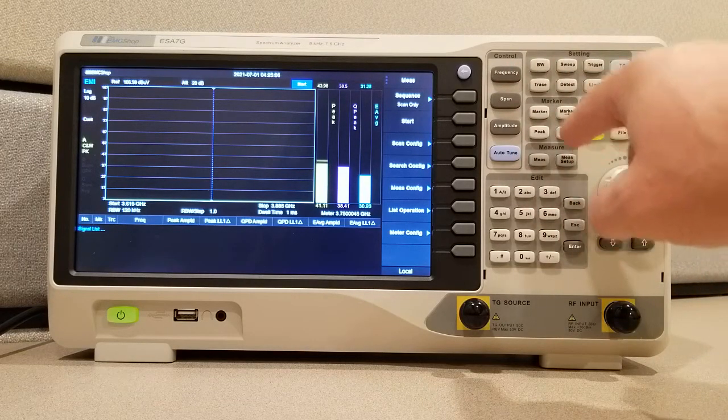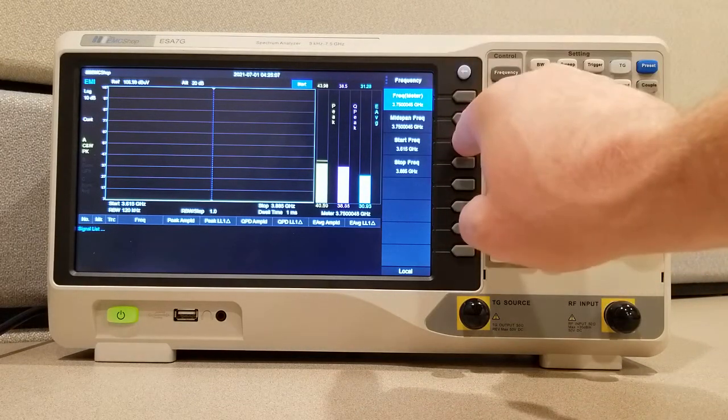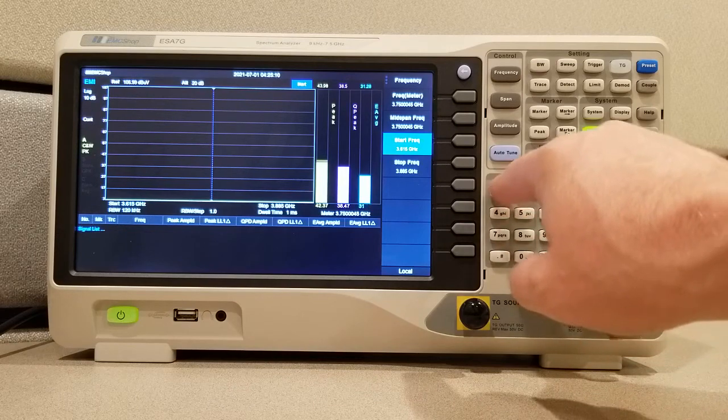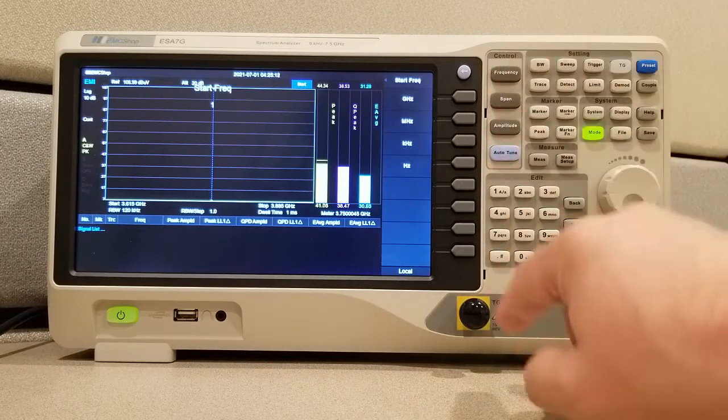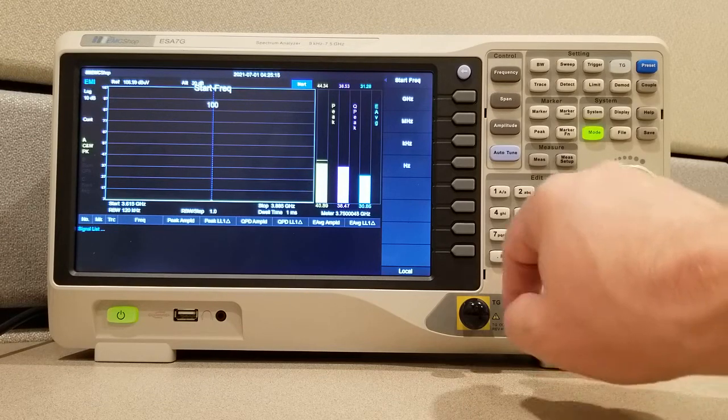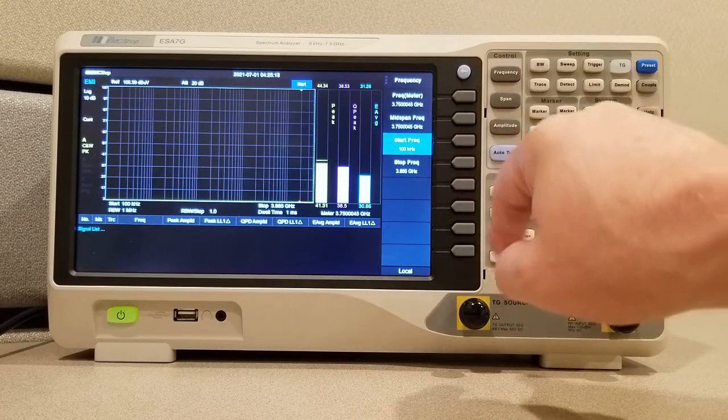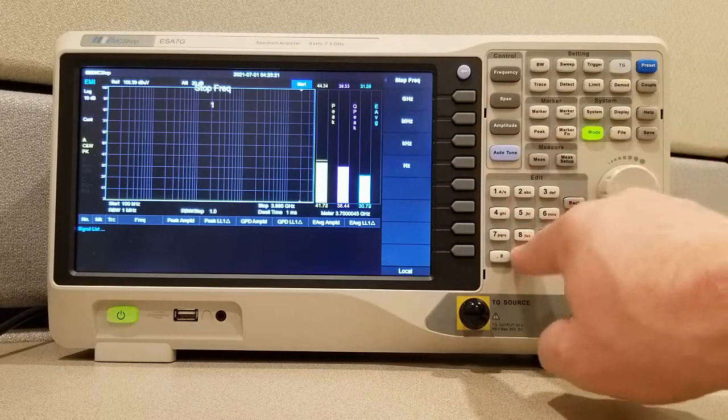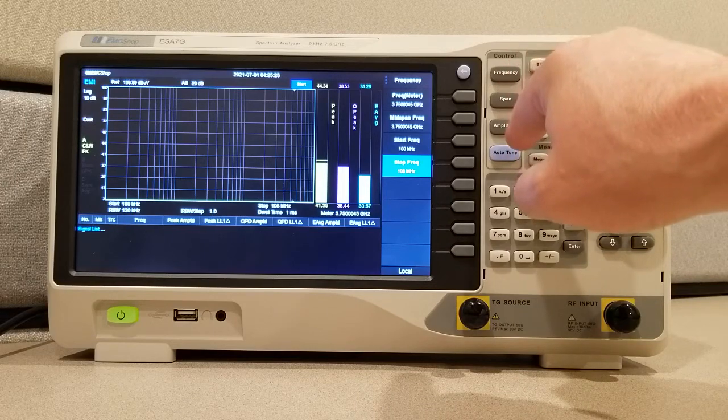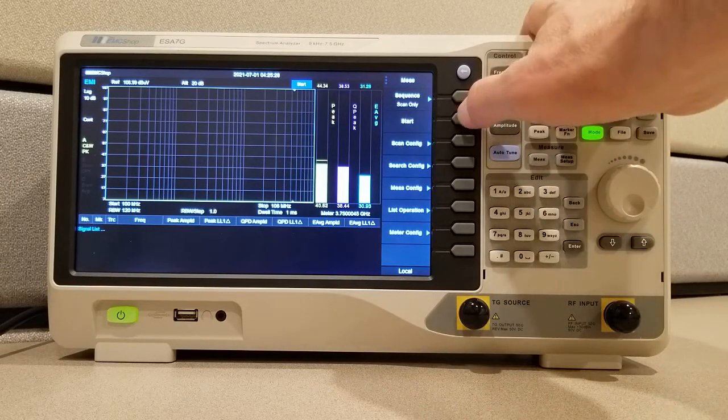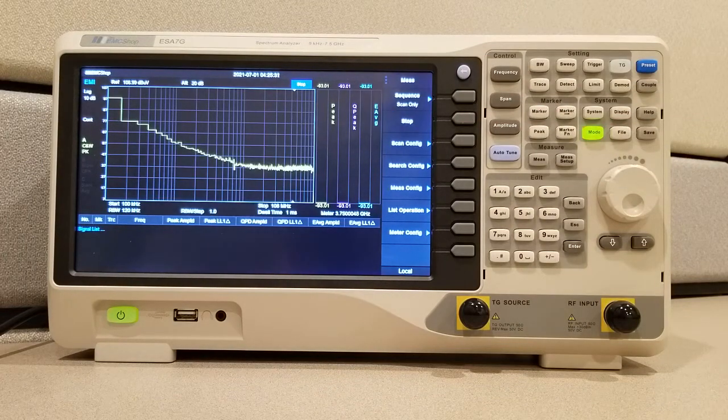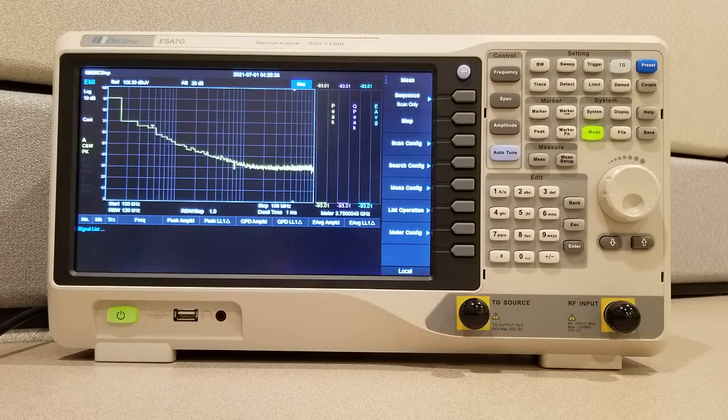Before we add the files, let's set our frequencies up to where we're going to be observing, which in this case we're going to add a LISN first, which ranges from 100 kilohertz to 108 megahertz. We're going to go to measure and we're going to do a quick scan just to get a baseline of where the trace is at this time.